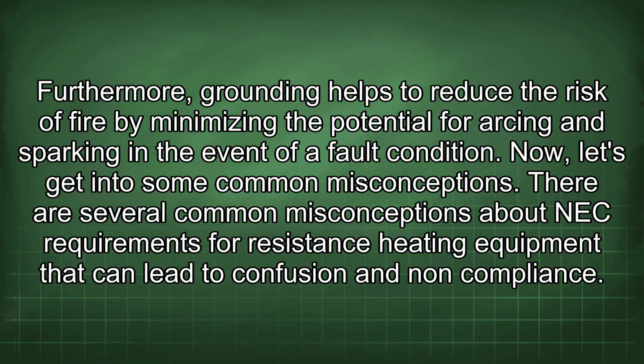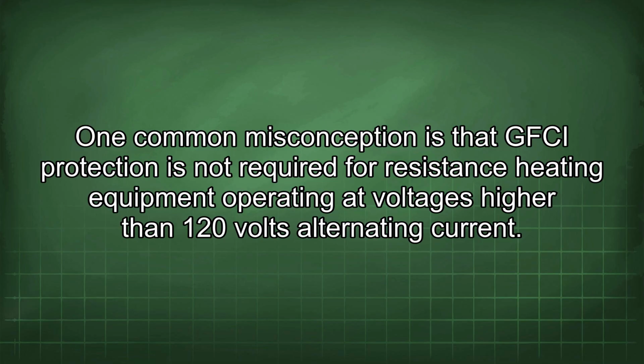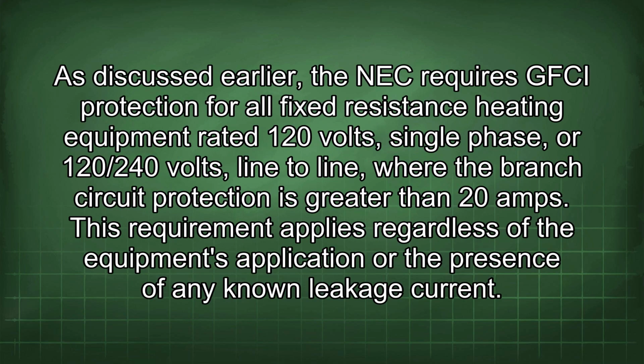There are several common misconceptions about NEC requirements for resistance heating equipment that can lead to confusion and non-compliance. One common misconception is that GFCI protection is not required for resistance heating equipment operating at voltages higher than 120 volts alternating current. As discussed earlier, the NEC requires GFCI protection for all fixed resistance heating equipment rated 120 volts single phase or 120/240 volts line to line, where the branch circuit protection is greater than 20 amps. This requirement applies regardless of the equipment's application or the presence of any known leakage current.